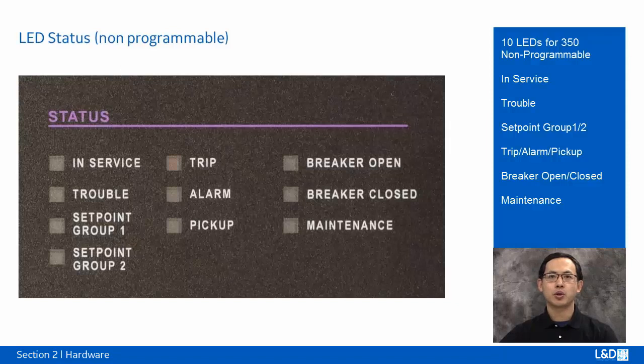Trip LED will turn on to red color when the relay detects a fault and sends a trip command to the trip output relay. The LED will reset by the reset push button or the software when the fault condition has cleared.